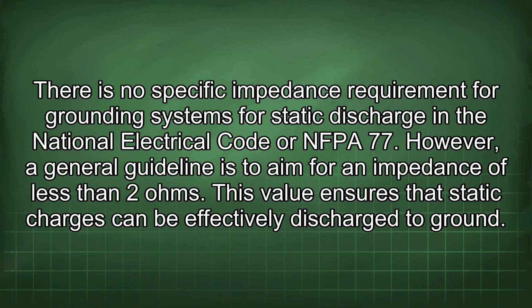There is no specific impedance requirement for grounding systems for static discharge in the National Electrical Code or NFPA 77. However, a general guideline is to aim for an impedance of less than 2 ohms. This value ensures that static charges can be effectively discharged to ground.